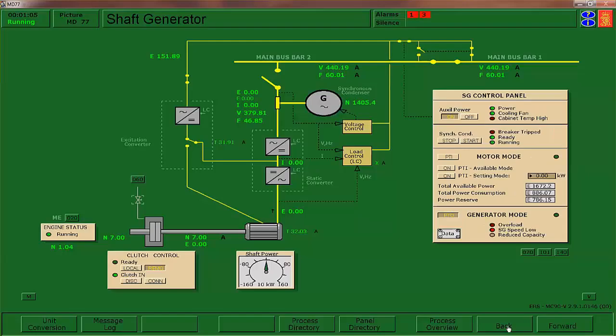Now let's go back for a second. Very briefly, this is a shaft generator that's being run off the main shaft through a tunnel gearbox, so it is going to run at an actual RPM higher than the main engine. The AC output of the generator goes through what they're calling a static inverter here. It's rectification, from AC to DC, with no frequency component. Then electronically, it goes through an inverter that uses modern power electronics to convert DC power into 440 volts, 60 hertz, three-phase. That is fed out of the shaft generator, and any other generator can be connected up to that, and they'll play very well together.